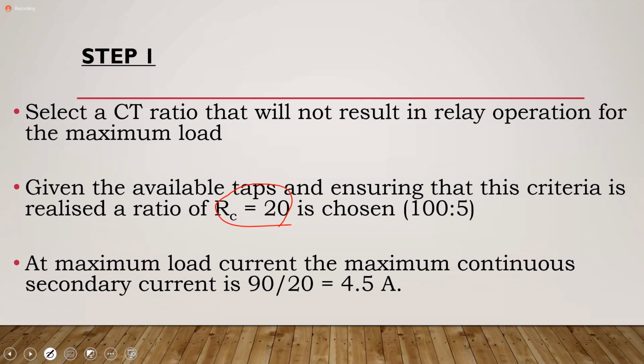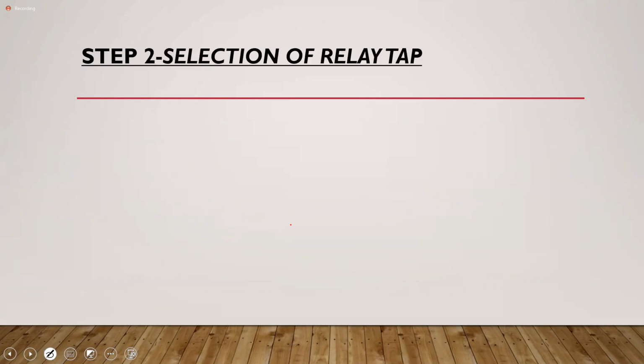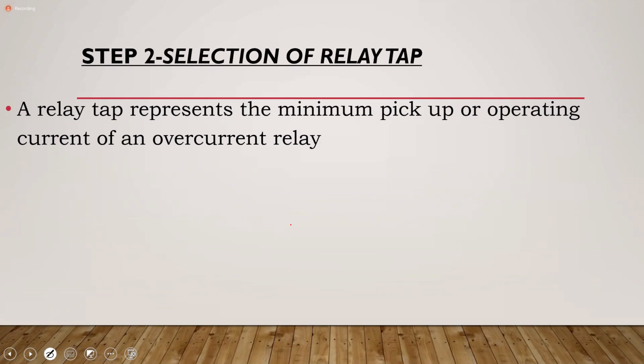But the point that we want to make here is that the system must operate while the maximum load is being supplied. So in setting your tap, you consider the maximum load. The maximum load is 90 amperes. So 90 over 20 gives us 4.5 amperes. So we want to next select the relay tap. We know that definition, okay? And the tap that you select must ensure that you can supply the maximum current. Everybody with me? Yes, sir.